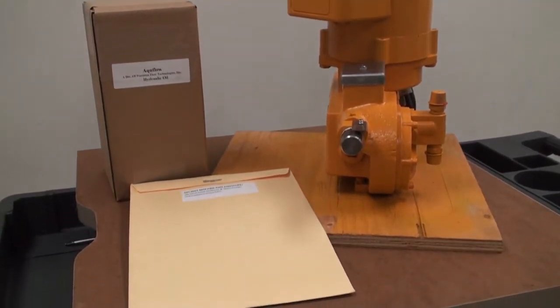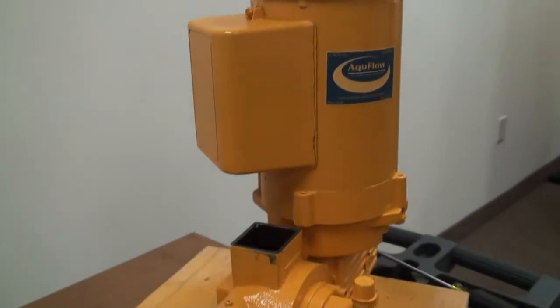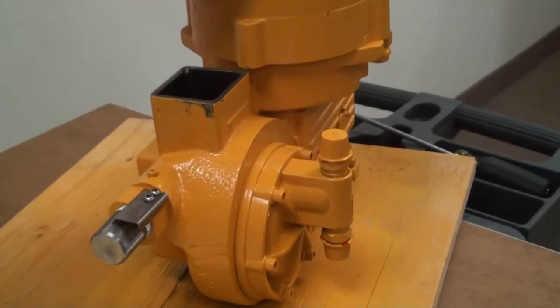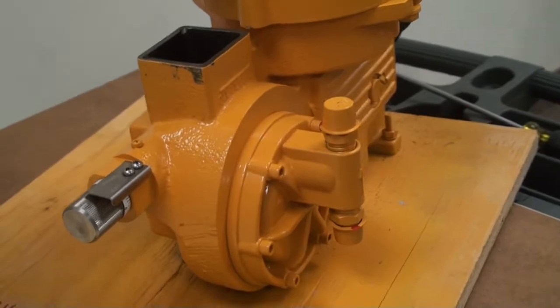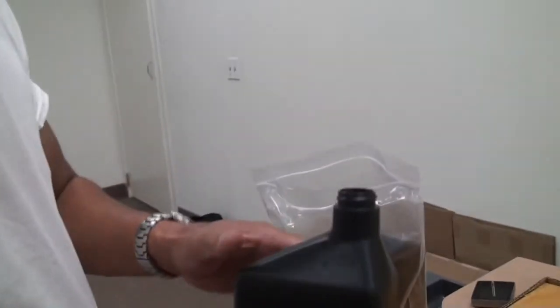All AquFlow pumps are hydraulically balanced diaphragm metering pumps. That means that the main medium of operation of the pump is hydraulic oil, which not only lubricates the internals of the pump, but also pressurizes and depressurizes the diaphragm to stroke back and forth.